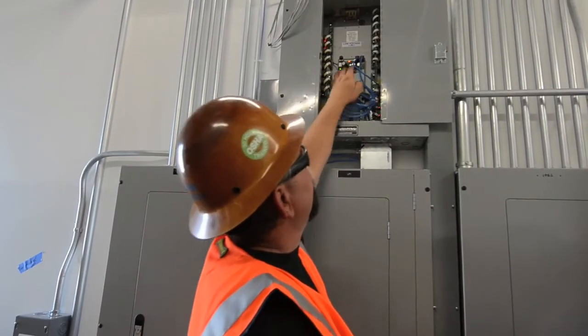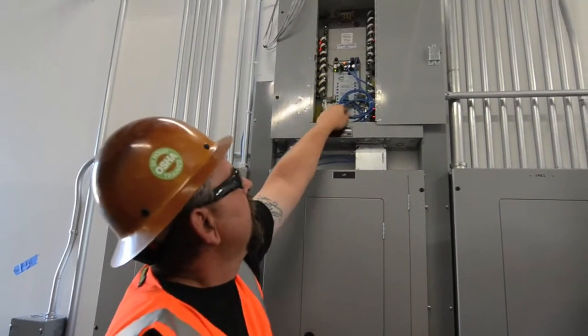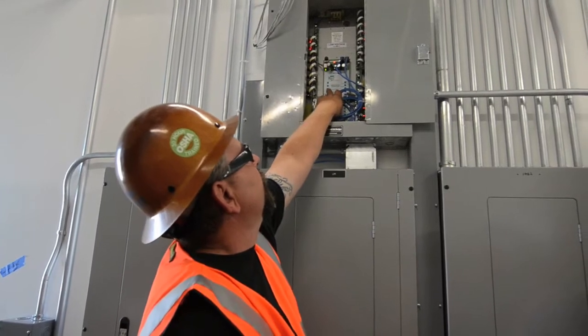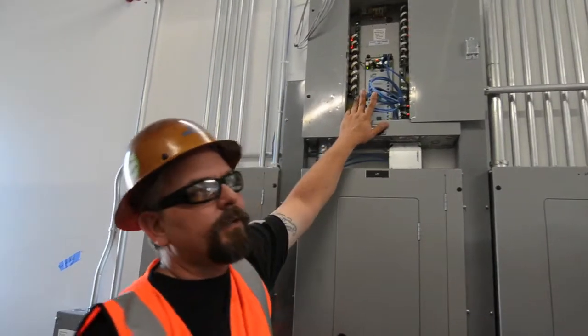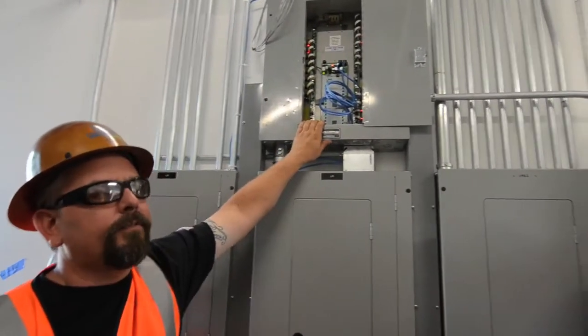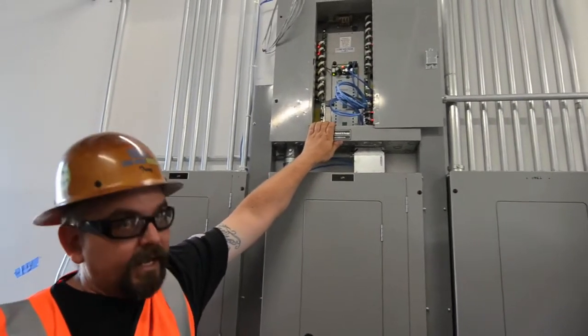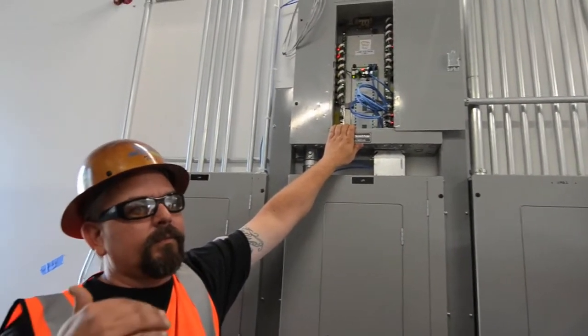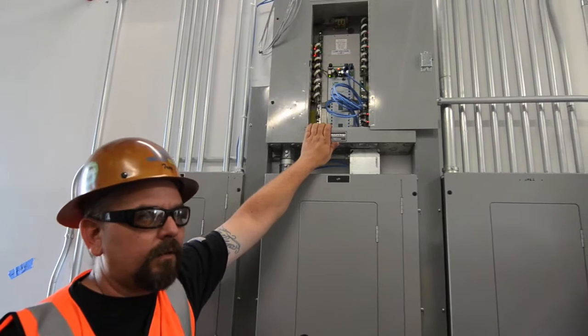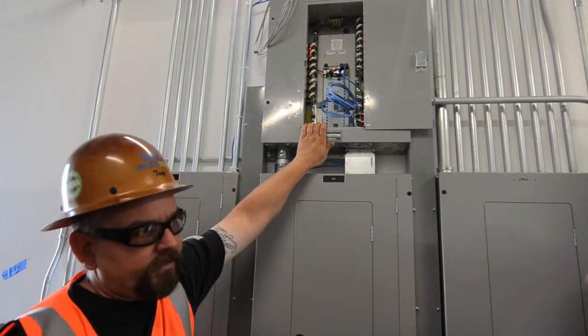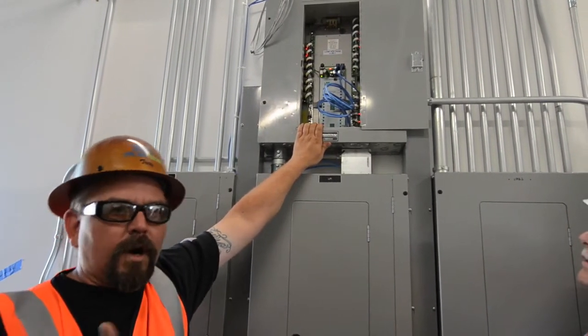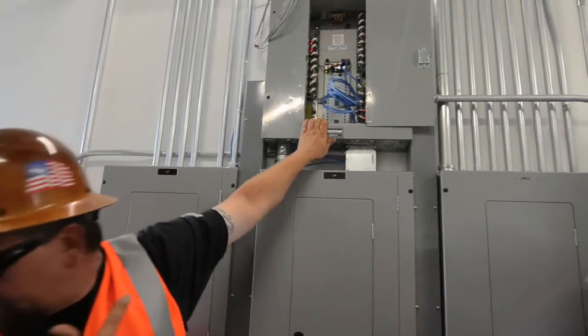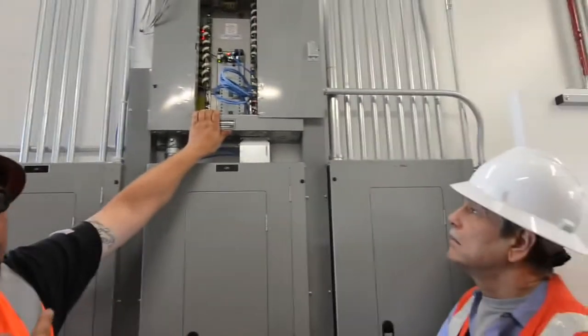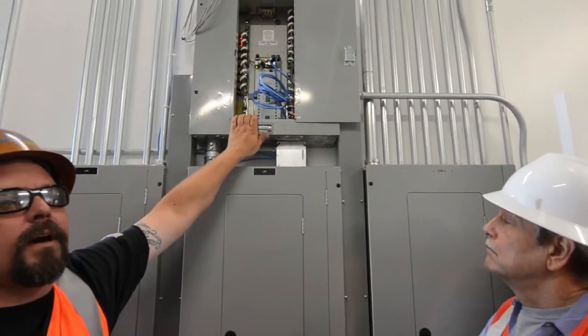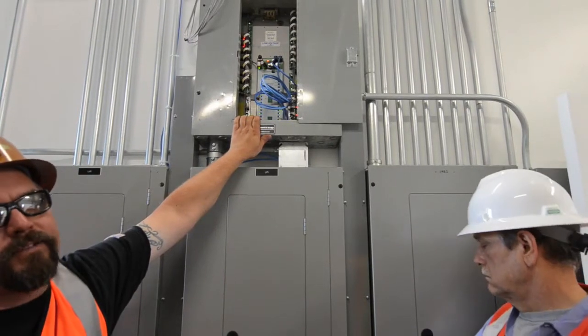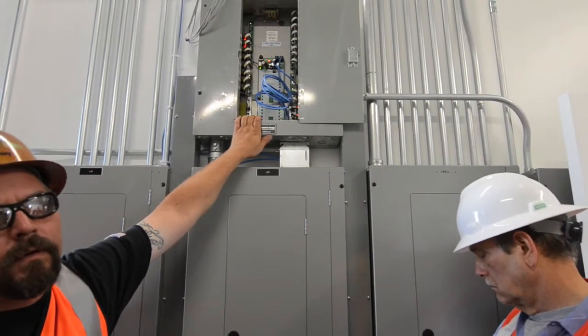One other thing I may have forgotten to mention: if I push relay 5, or any relay, on during the day that's currently off, it'll stay on for today, but once the photocell goes through its dusk-till-dawn cycle, tomorrow that relay will no longer be on manually. It'll only stay on for that day and that cycle of the photocell.